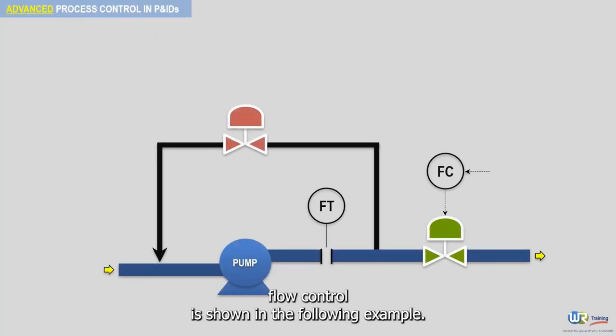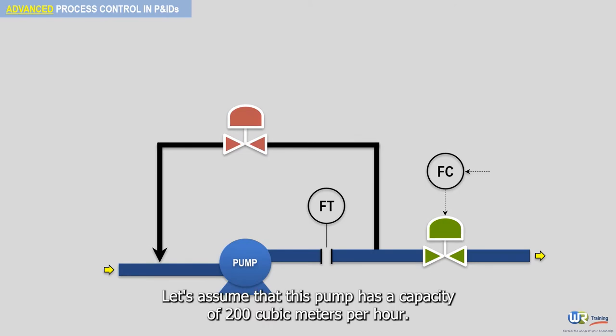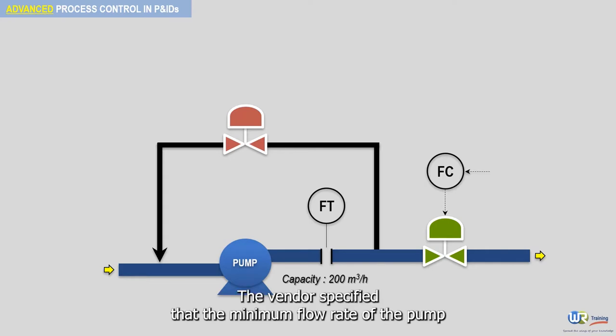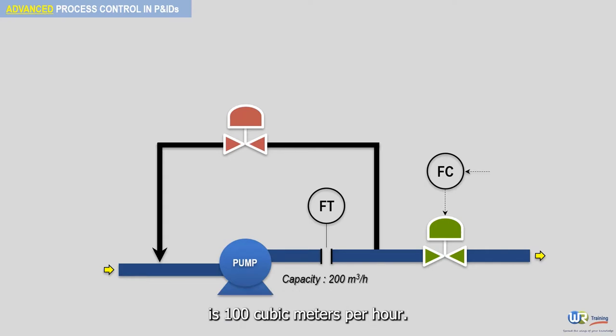The concept of minimum flow control is shown in the following example. Let's assume that this pump has a capacity of 200 cubic meters per hour. The vendor specified that the minimum flow rate of the pump is 100 cubic meters per hour.